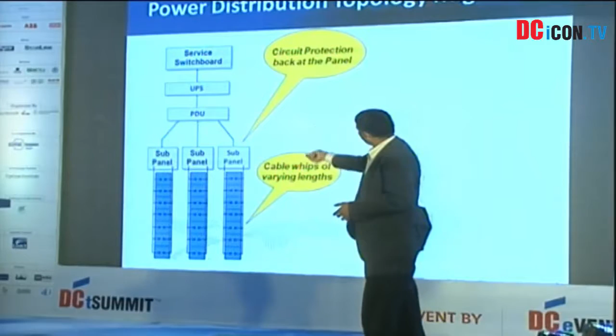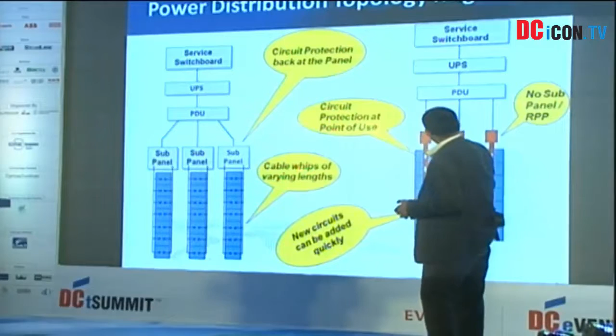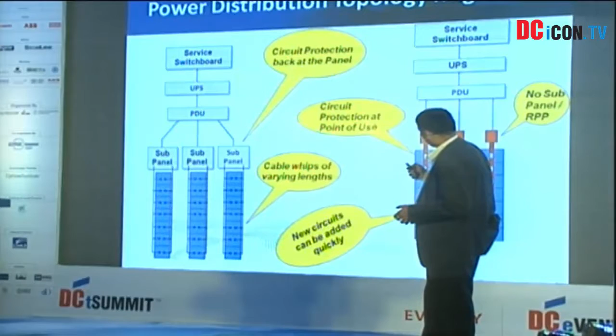Today we are talking about a distribution that is more organized and flexible, meaning power needs to be available at any given point under whatever circumstances. So you still have a service board, UPS, and PDU, but instead of going to a sub panel or RPP, you eliminate that with a feed unit, and from the feed unit, the bus bar extends directly all the way to the end of your individual cabinets, eliminating the extra space needed at the end of the row.